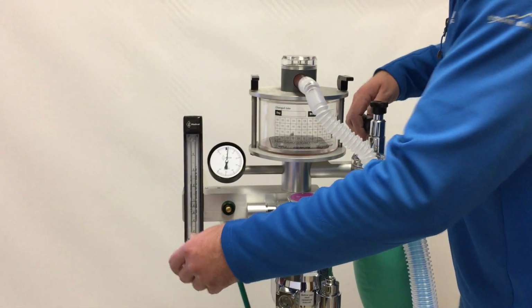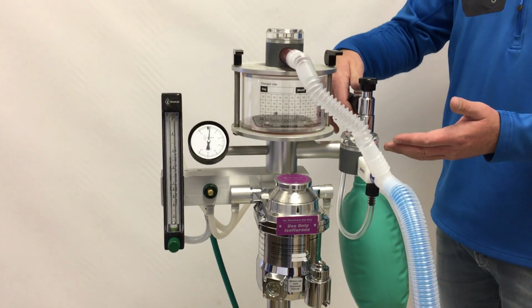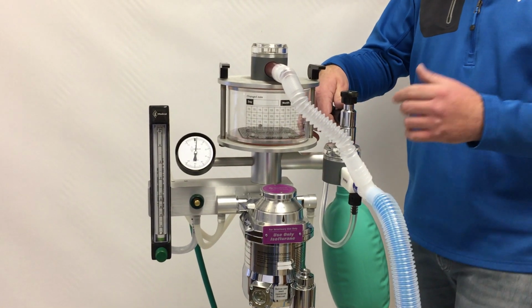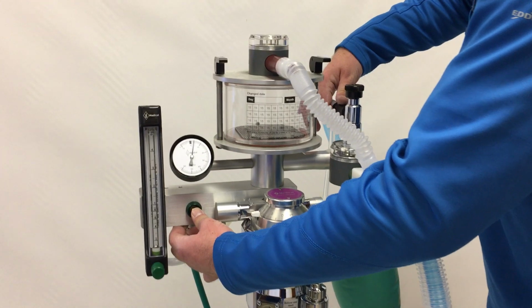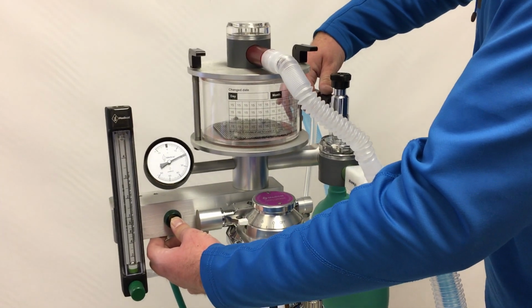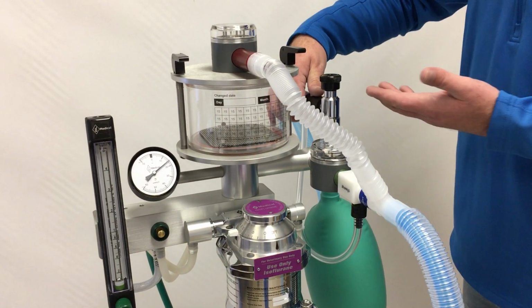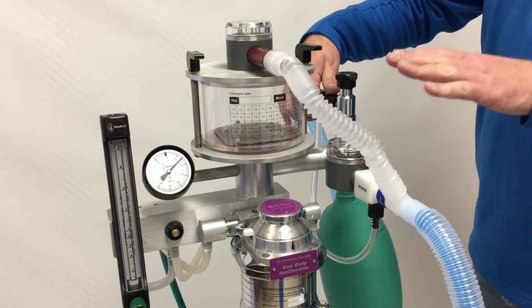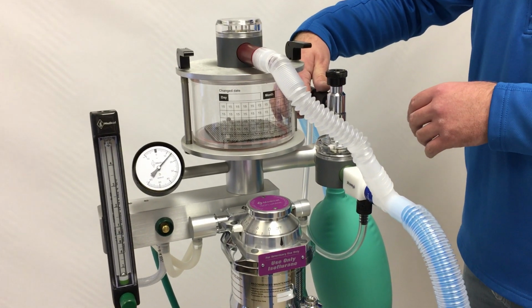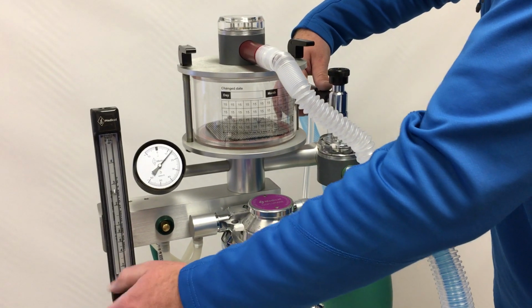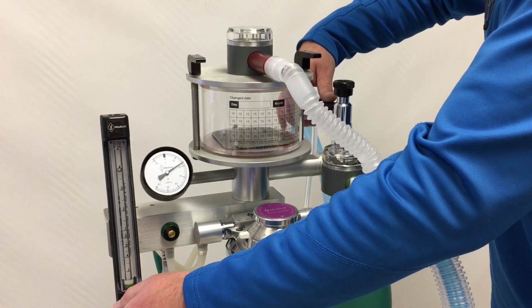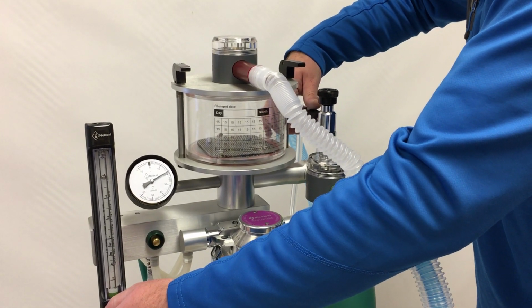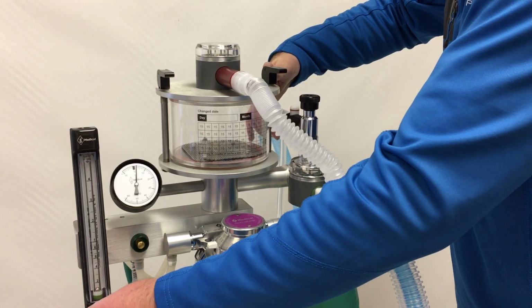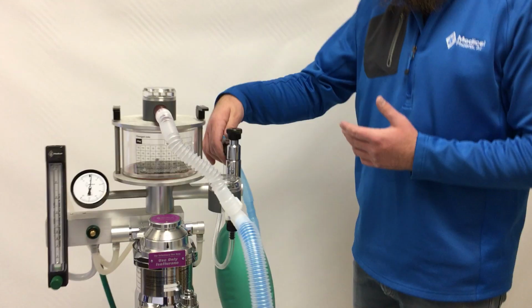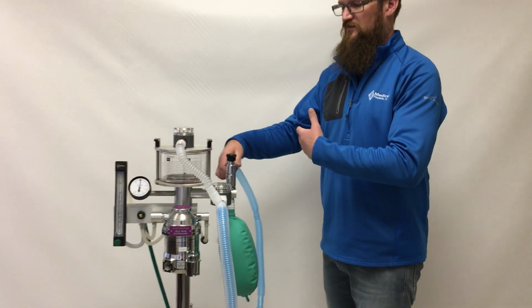Another situation where you could have a problem where the valve will vent is if the occlusion valve is held closed. We can build up pressure and it will vent pressure. In that case, it operates completely independently of the rest of the components of the anesthesia machine. If we add flow in, it will continue to vent, and I can release, if I've forgotten or if it's malfunctioned, the occlusion valve and relieve that pressure.